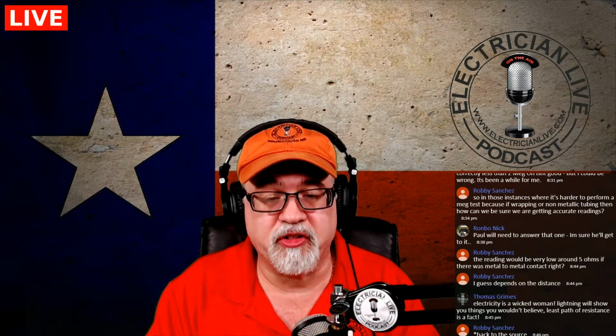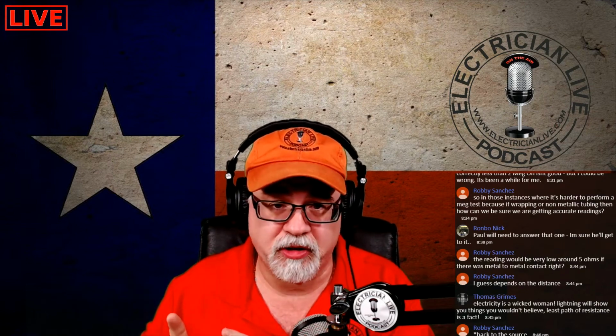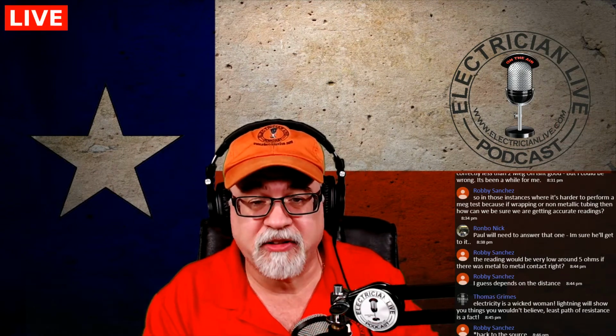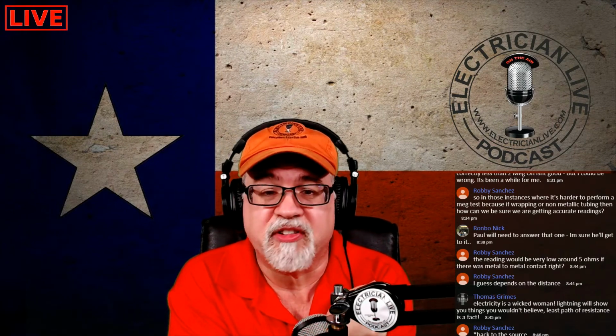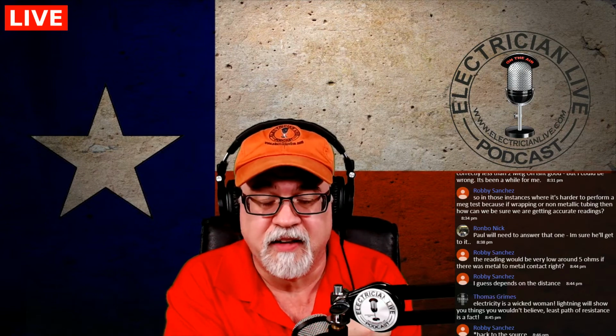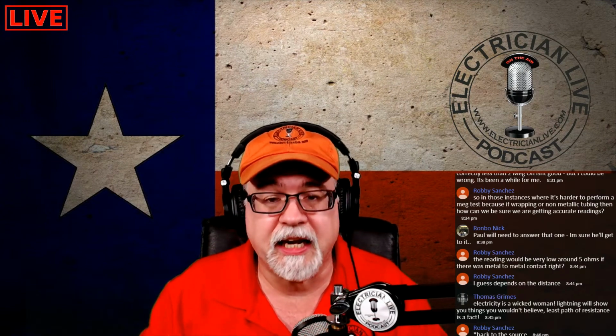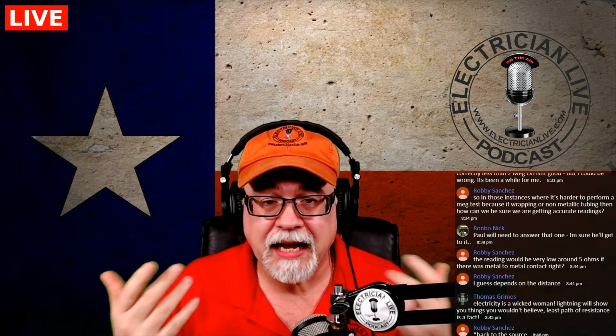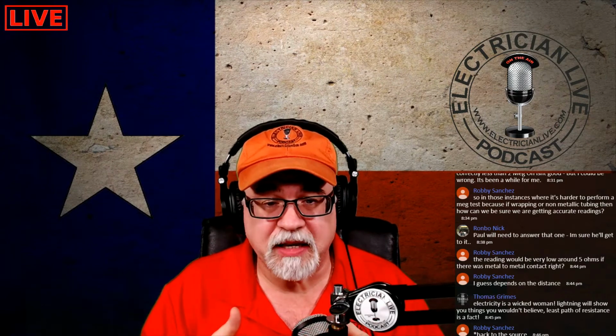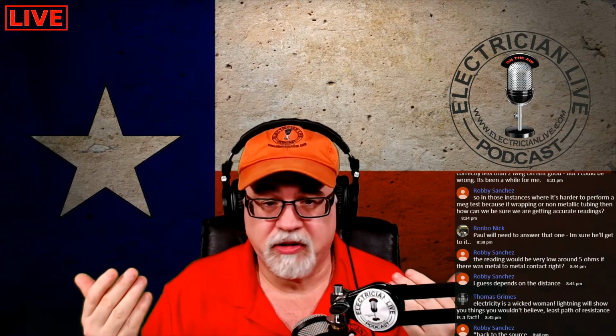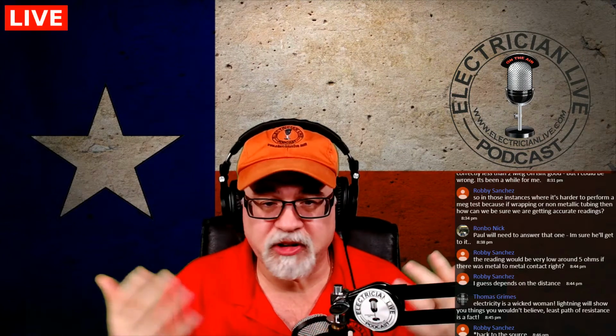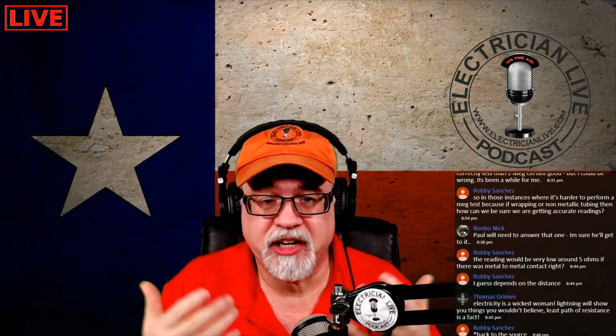Okay? But even with that said, I have seen conductors that get pretty darn damaged that were thrown into a raceway. I've seen this because of where I work. I've seen wires thrown in a non-metallic raceway that were severely damaged. We've tested this, and you test it with the MEG reading, and it comes out fine. Why? Because only the one is damaged, the others are not damaged. There was no way to get a return path on it. So how could you get a reliable reading?